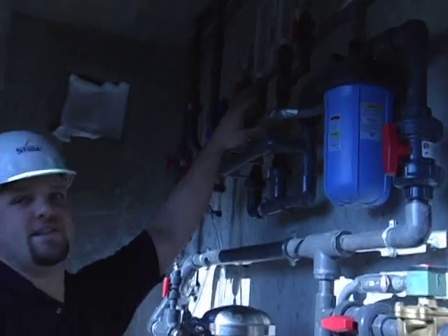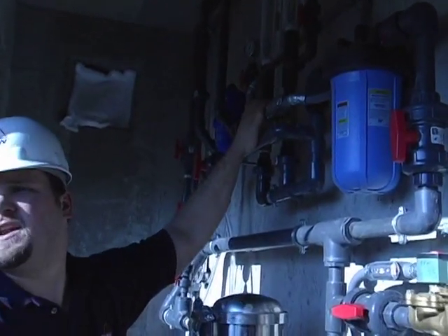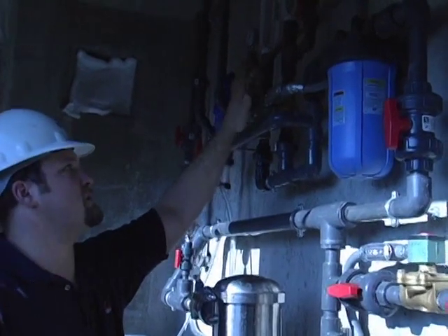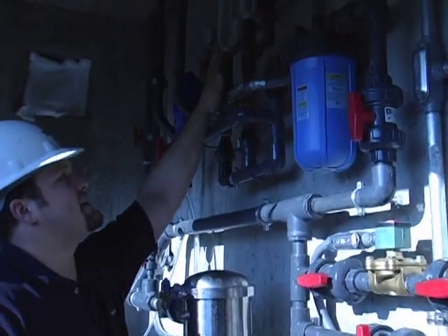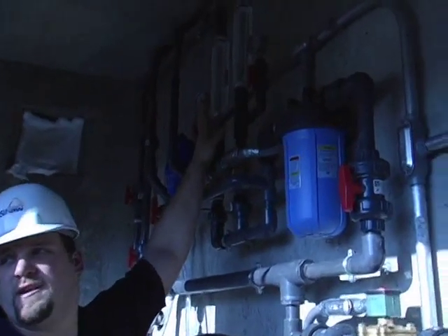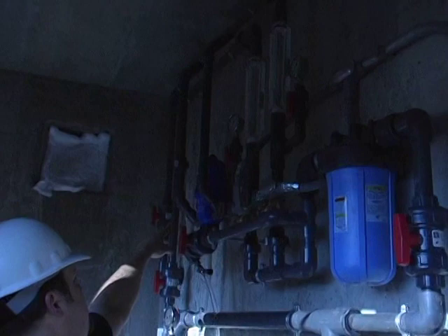At first, this is the upper irrigation solenoid. This is one of the solenoid valves that's operated off a timer in this control panel here. When that timer opens this valve, you'll be able to see the flow that you're getting through your line with this rotometer here, and also the pressure through your line with this pressure gauge. It goes up, around, back down.